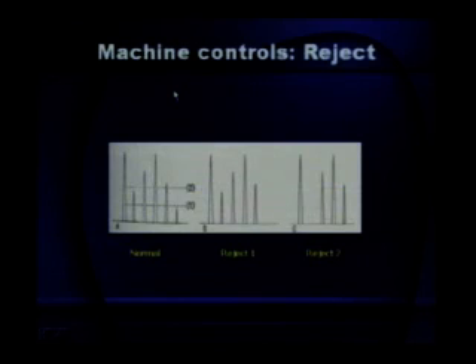Now, unlike time gain compensation and gain, in reject we do not change the signals, but we set a threshold beyond which the signals are displayed. This is normal without any reject. All the echoes are being displayed. If we set a reject level or threshold at this point 1, this dotted line, this will eliminate this echo, and this echo signal will not be displayed, as in the case in B. If we raise the reject level or the threshold, this echo will also be eliminated, so only these will be displayed.